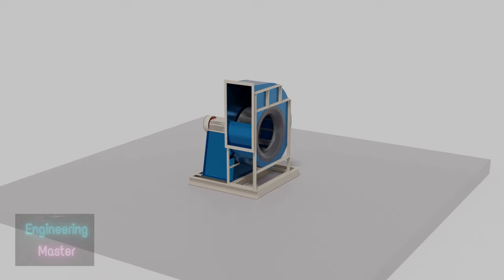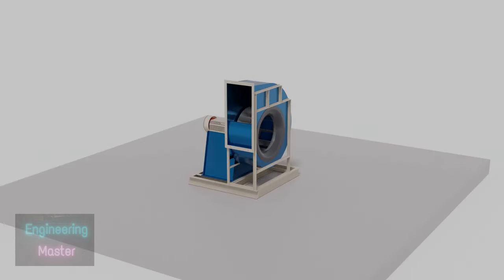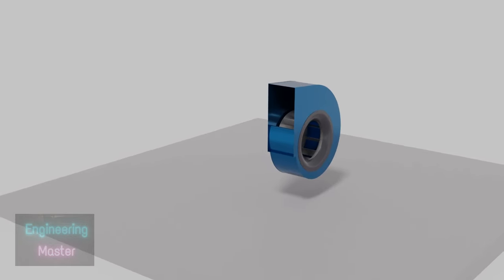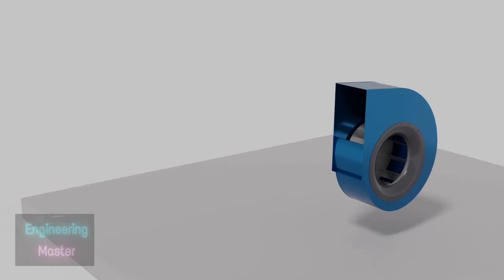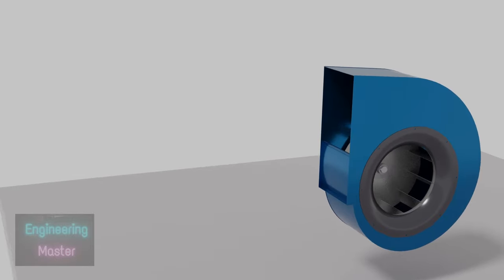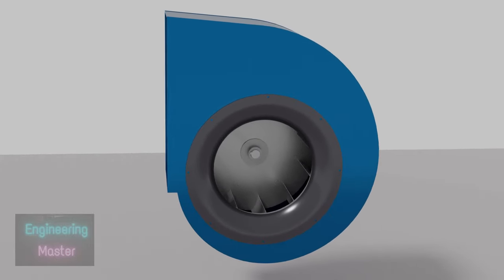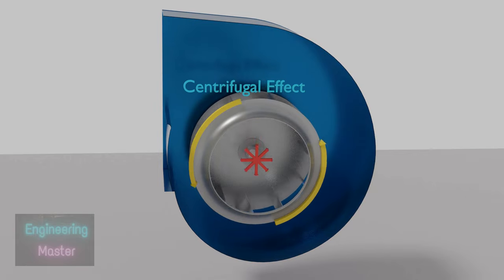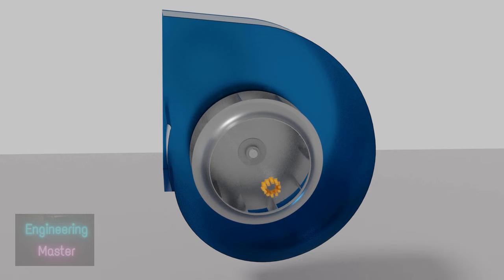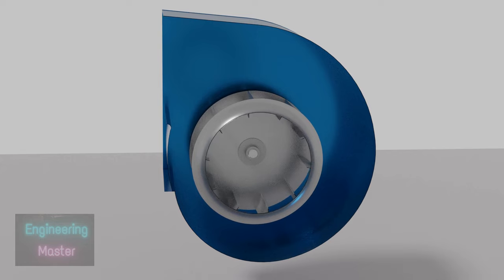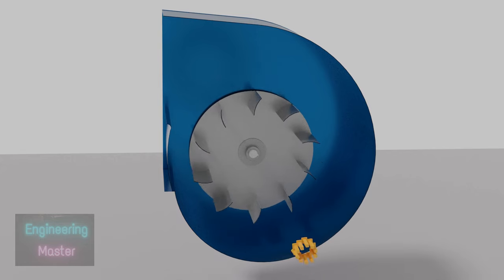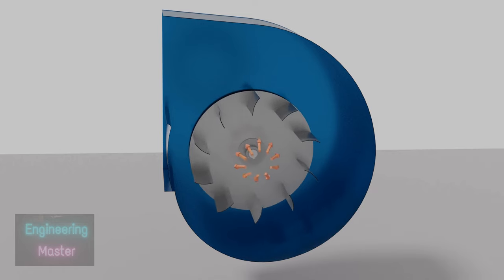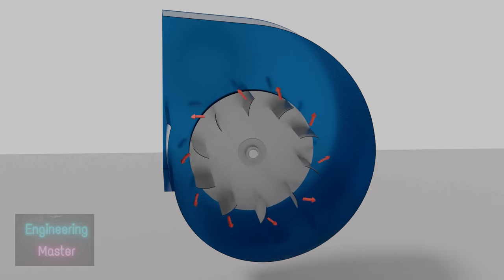Now we will see the working principle of centrifugal fans. In centrifugal fan the operating principle is a combination of two effects: centrifugal effect and deflection of airflow by the blades. Centrifugal force is the apparent outward force on a mass when it is rotated. Here the air entering inside impeller experiences the centrifugal effect, and it will be pushed outwards. If we look closer we can see that first the air is being pushed outwards, and then it's deflected by the impellers.